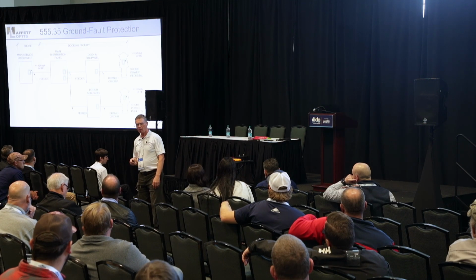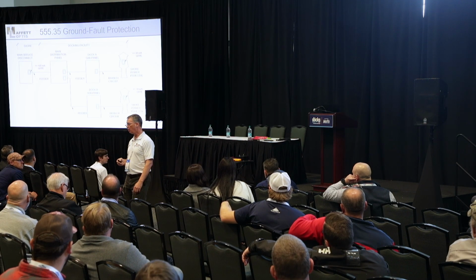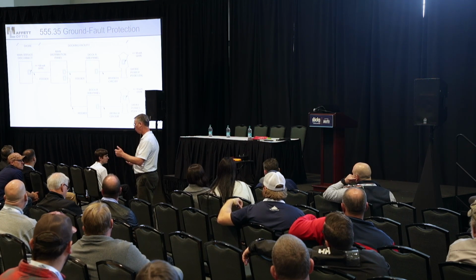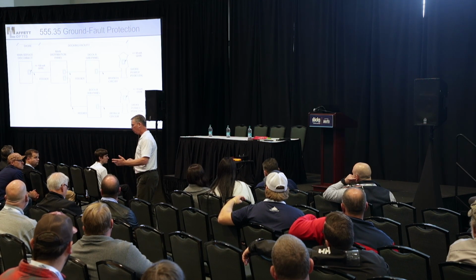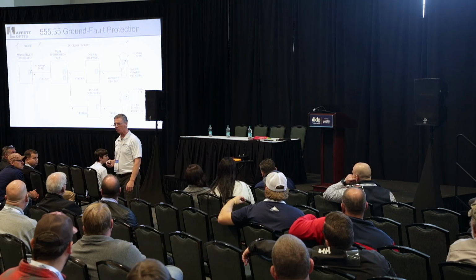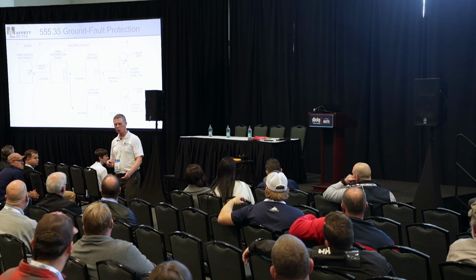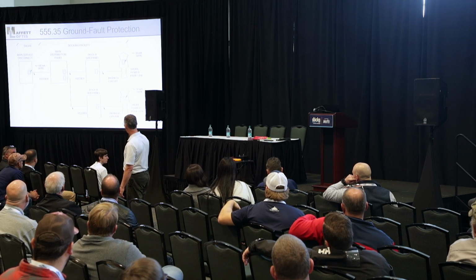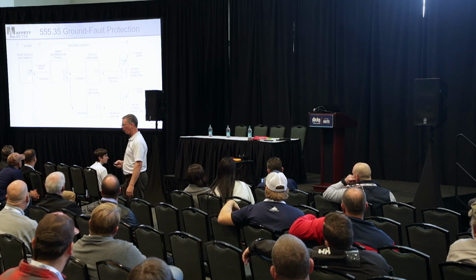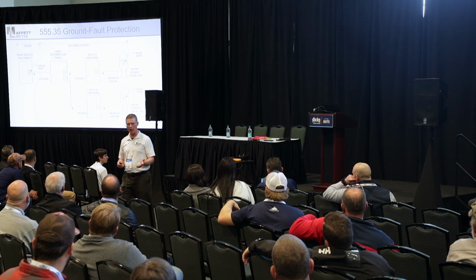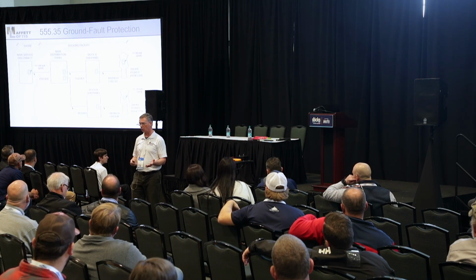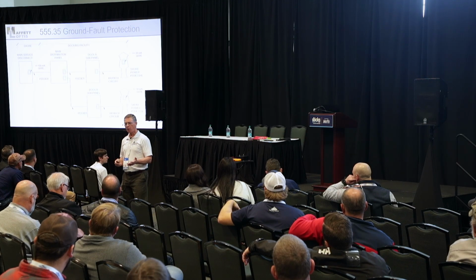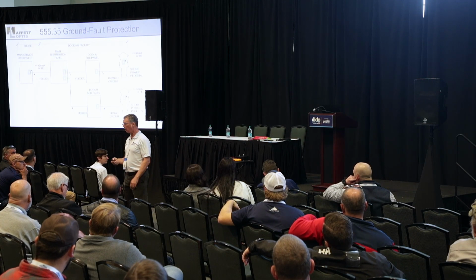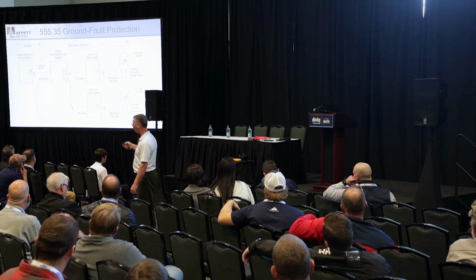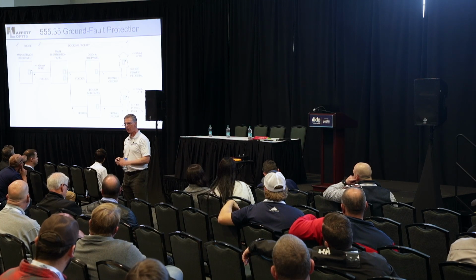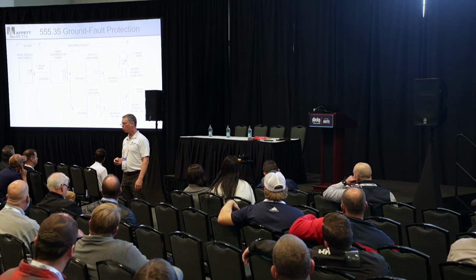For example, say a boat comes in, plugs in, turns the breaker on, and his inverter is leaking 300 milliamps of current. What's going to trip? Is it going to trip there at 30 milliamps, or at the 100 milliamps? If the boat's leaking 300 milliamps, it has opportunity to trip at both locations, right? So if it's not coordinated, it might trip up here and your entire marina goes down for one bad boat. If that happens, which boat is it?